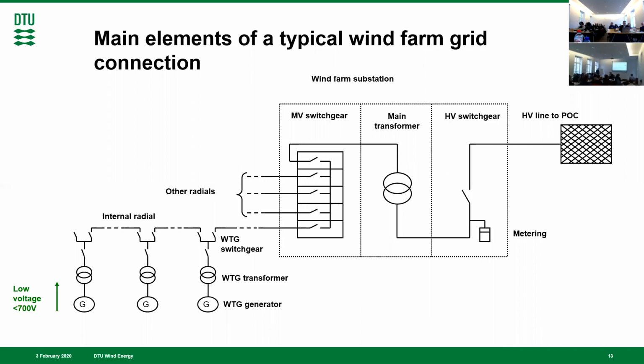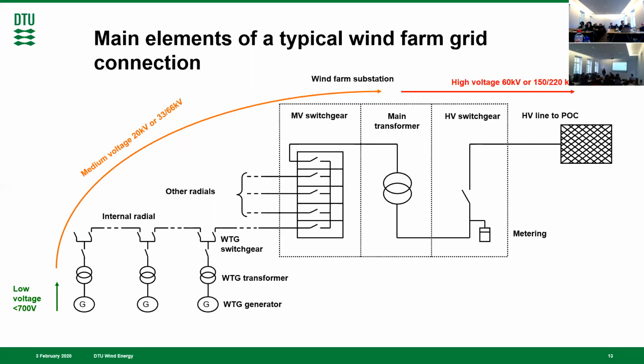Wind turbines are still built at low voltage inside. Then at each step you increase the voltage to medium voltage, around 20 kV to 66 kV, with the higher values more common offshore than onshore. Then you have the largest one, the high voltage connection to the point of connection, which for offshore I think of as the shore point. So it's always increasing, and there's a significant amount of electrical equipment outside the wind turbines, in the wind farms.